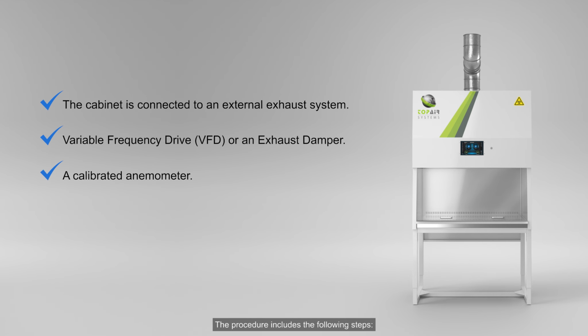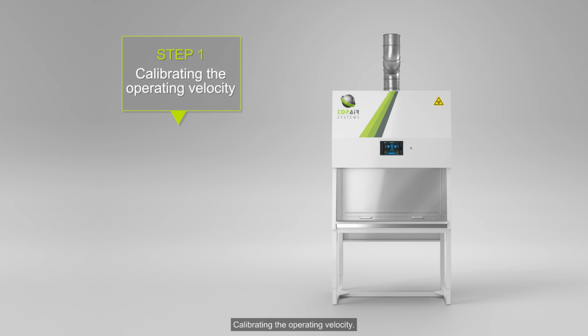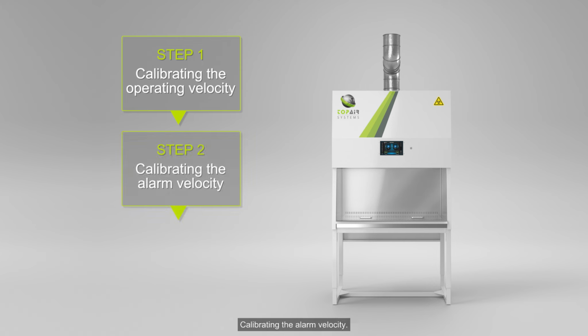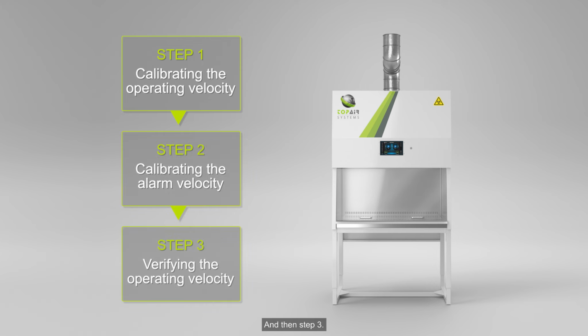The procedure includes the following steps. Step 1. Calibrating the operating velocity. And then Step 2. Calibrating the alarm velocity. And then Step 3. Verifying the operating velocity. All three steps must be completed to calibrate the BioSafety cabinet successfully. Now we will perform Step 1 and calibrate the operating velocity.